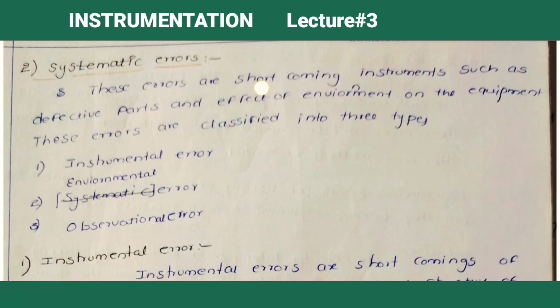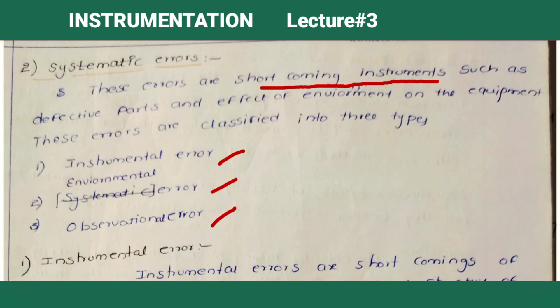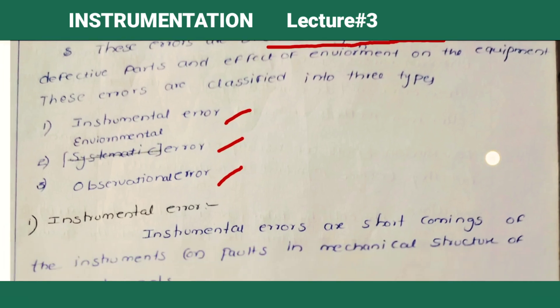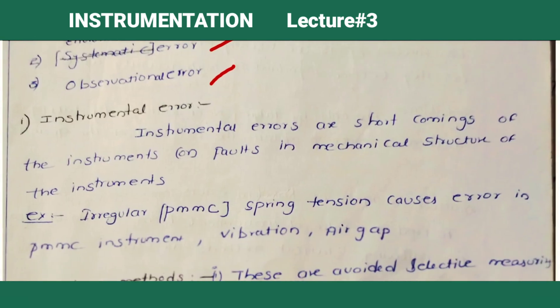Systematic errors are shortcomings of the instrument — internal or inbuilt faults that may appear in the instrument. Instrumental errors are the shortcomings or defective faults in the instrument's mechanical structure. For example, irregular PMMC spring tension can cause error in a PMMC instrument, as can vibration and air gap issues.